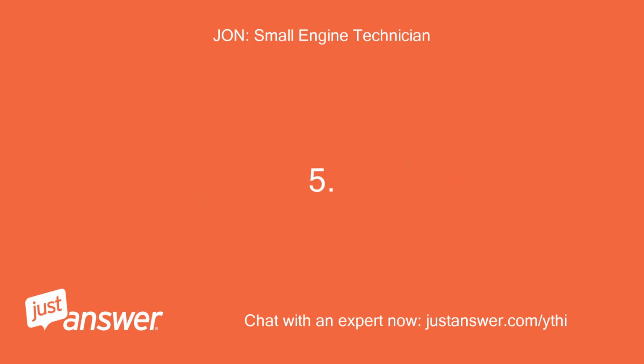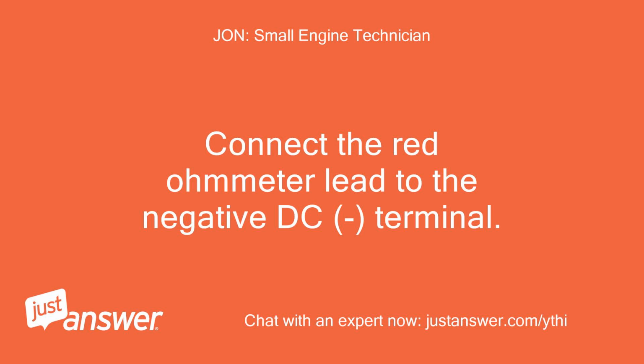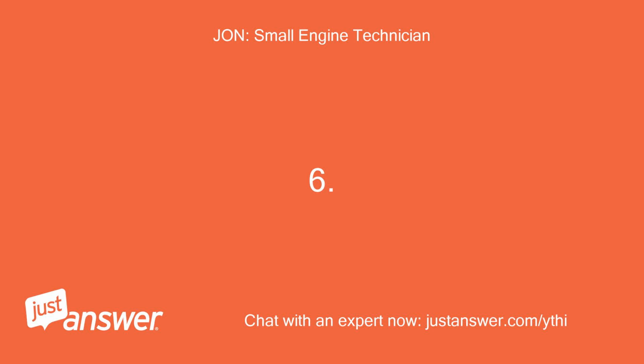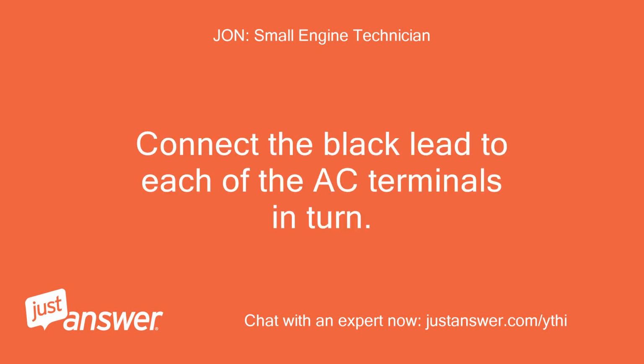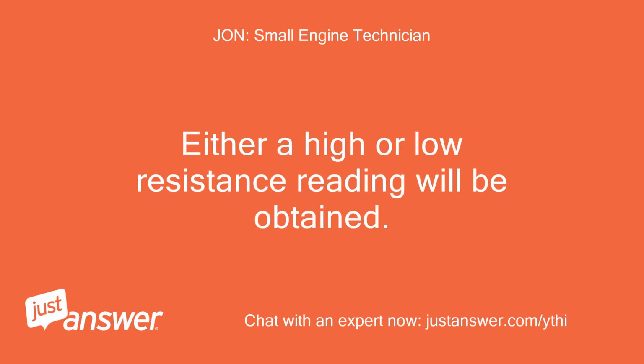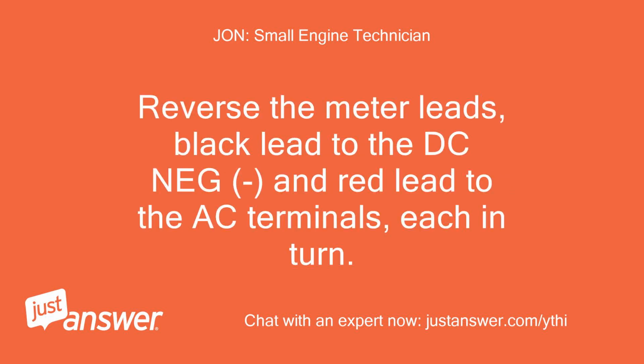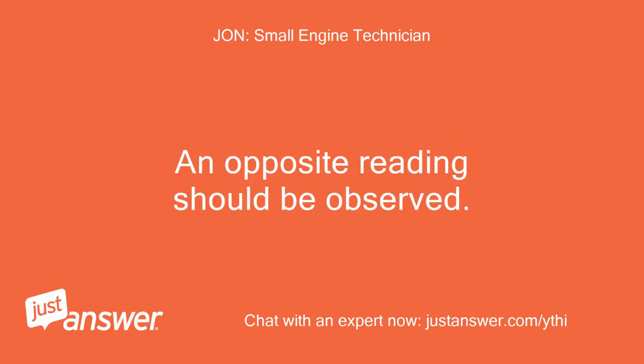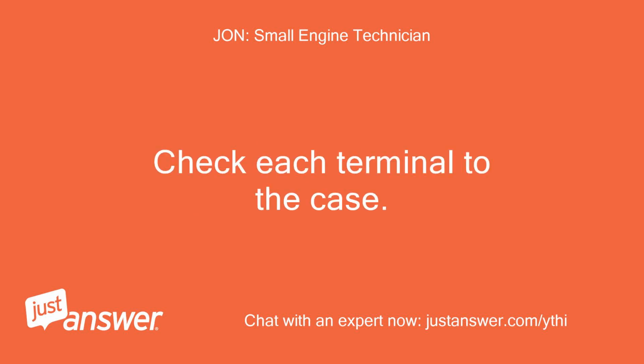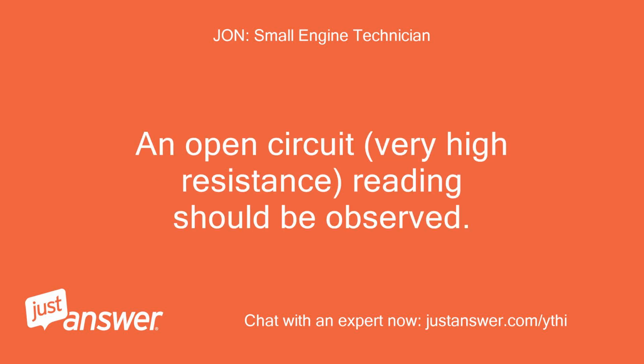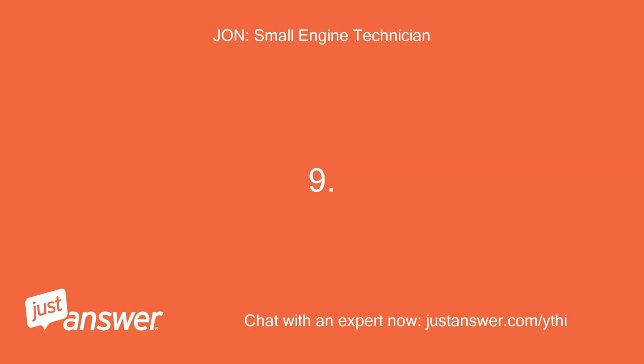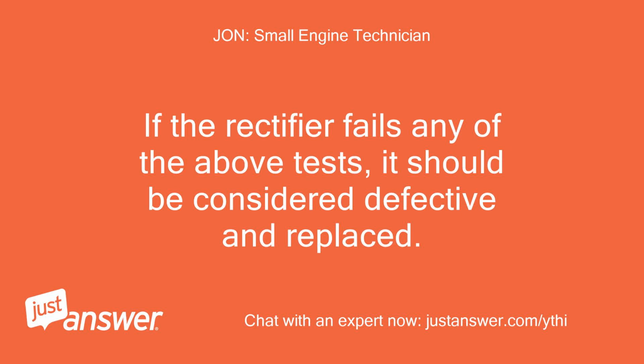5. Connect the red ohmmeter lead to the negative DC terminal. 6. Connect the black lead to each of the AC terminals in turn. Either a high or low resistance reading will be obtained. 7. Reverse the meter leads, black lead to the DC neg, and red lead to the AC terminals, each in turn. An opposite reading should be observed. 8. Check each terminal to the case. An open circuit, very high resistance, reading should be observed. 9. If the rectifier fails any of the above tests, it should be considered defective and replaced.